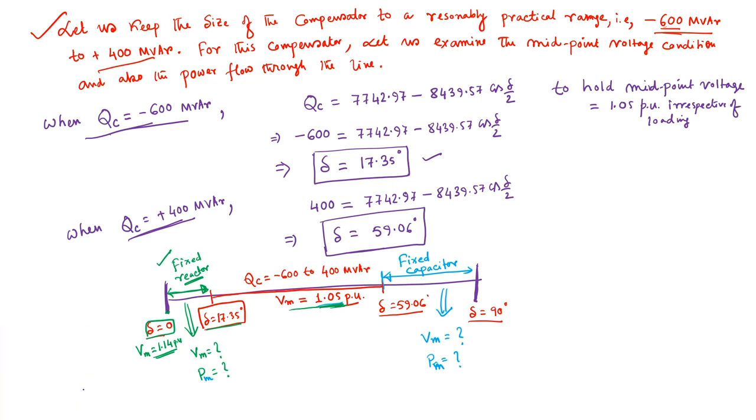Now if we summarize what we have learned so far, what we can write is: when delta is between 0 to 17.35 degrees, this compensator will act as a fixed reactor or fixed inductor mode.